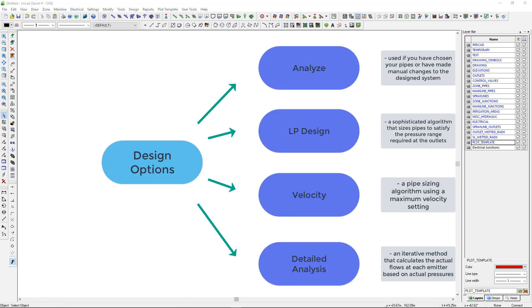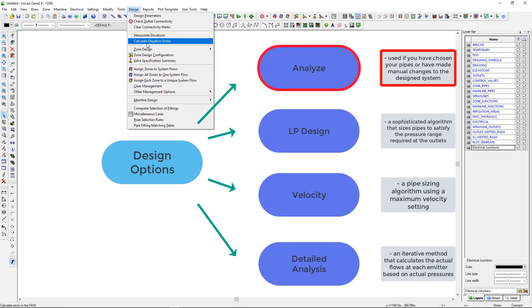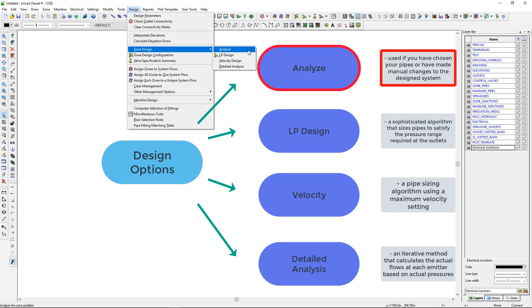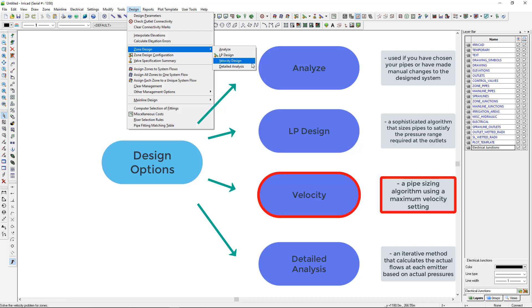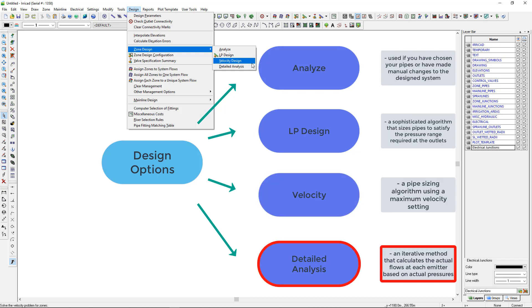The design and analysis options are: Analyze - use if you have chosen your own pipes or have made manual changes to the designed system. LP Design - a sophisticated algorithm that sizes pipes to satisfy the pressure range required at the outlets. Velocity - a pipe sizing algorithm using a maximum velocity setting. Detailed Analysis - an iterative method that calculates the actual flows at each emitter based on actual pressures.